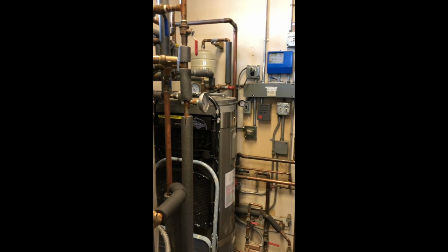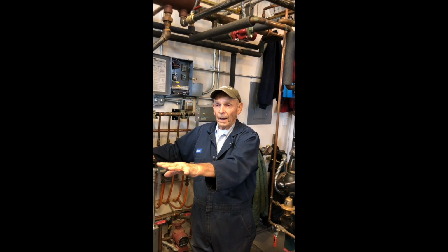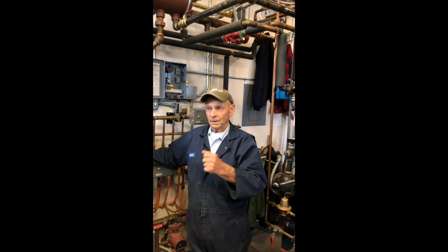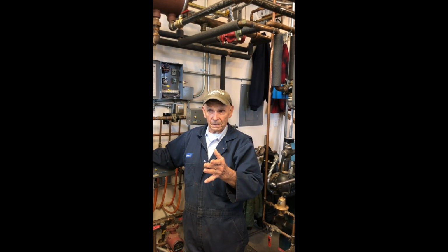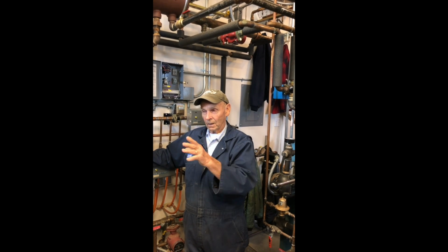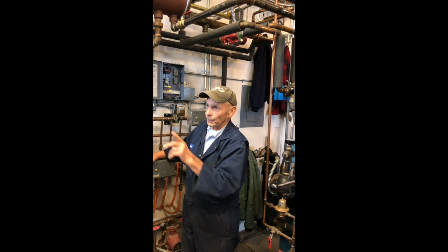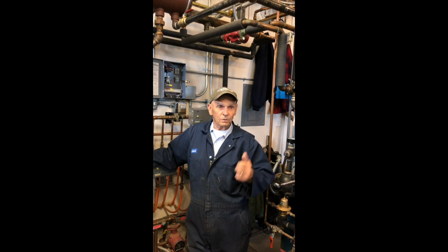It won't serve any more heat up there, and it won't continue to heat. So you have to kind of realize how much wood you need and how hot you want the boiler. As long as it's below 190 degrees, that won't happen. But as soon as it gets that hot, it will automatically, through a relay in here, bring on the domestic water pump to raise the temperature in the bonus room.